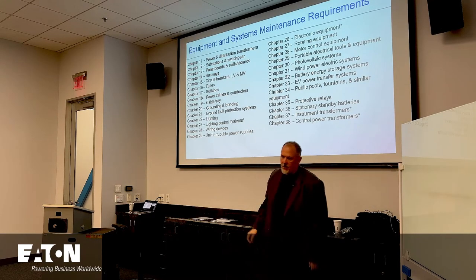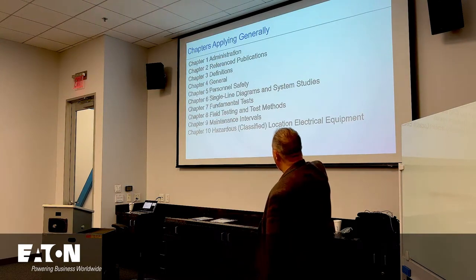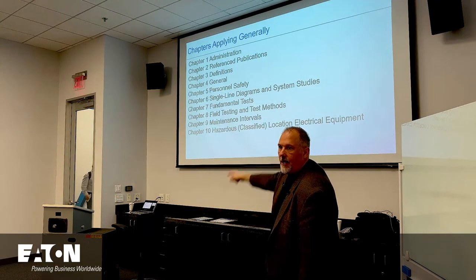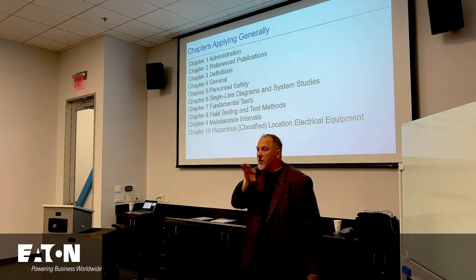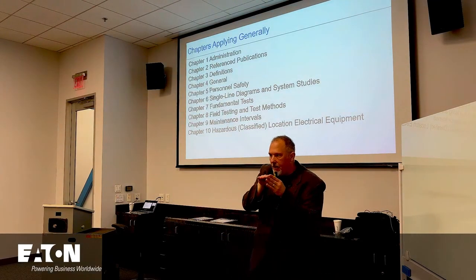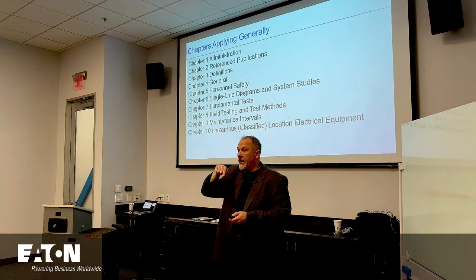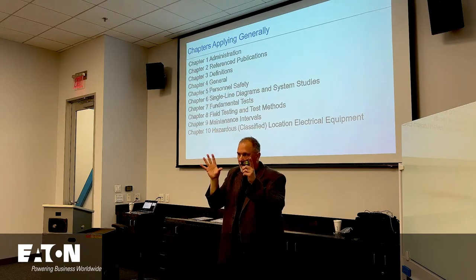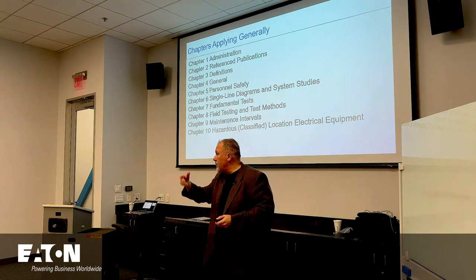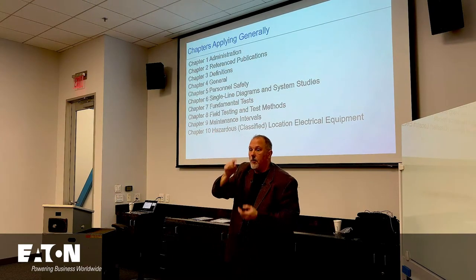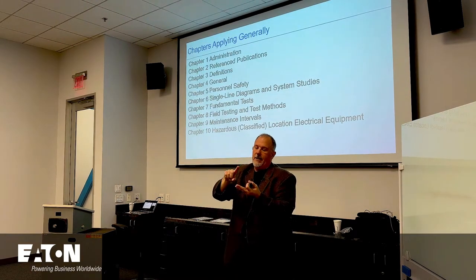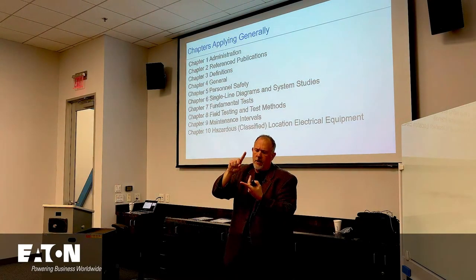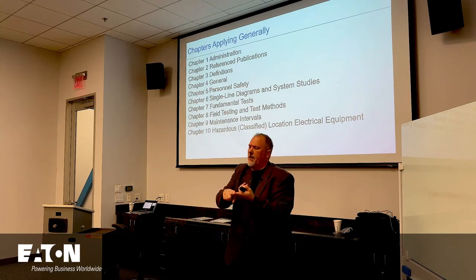So the way this works, you would go to the maintenance intervals, chapter 9. And you would say, okay, I have a circuit breaker or a fusible switch. You would go to that line and it'll tell you the frequency. It'll tell you how often should you do infrared or IR scanning or some method to determine the terminations, how often should you do a mechanical test, electrical test, mechanical, electrical, visual, and something else.